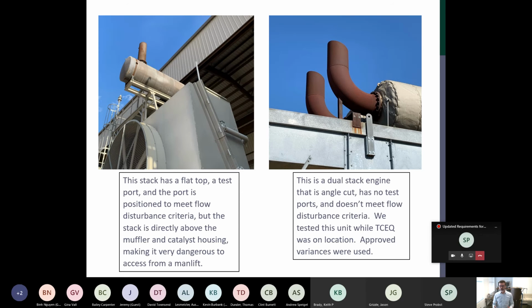We had to use some variances here to test this stack, by going over the top with some probes designed to sample from the best location that we could get out of this stack, and to get our pitot measurements at traverse points that would meet the method criteria. Again, we had to modify on the fly, but the variances that we used were approved. TCEQ came back and recommended that the operator modify their stack to be designed differently to overcome not only not having test ports and not meeting flow criteria, but also in how you would approach testing dual stack units.